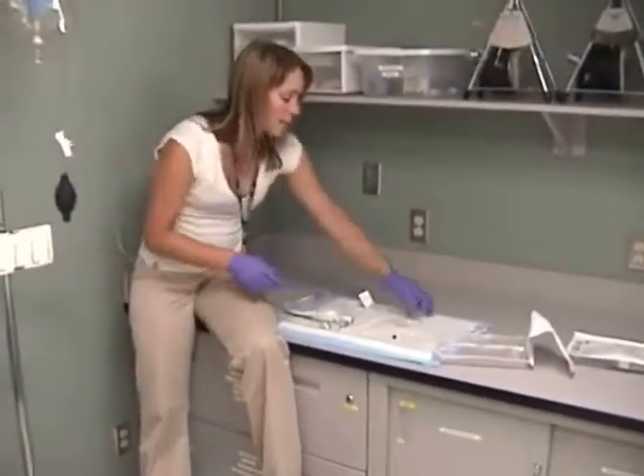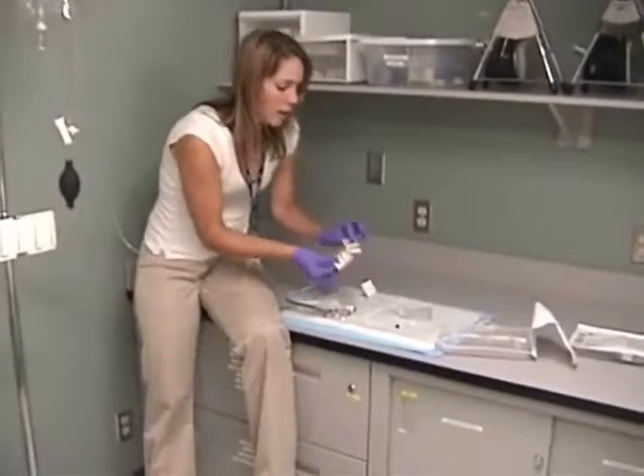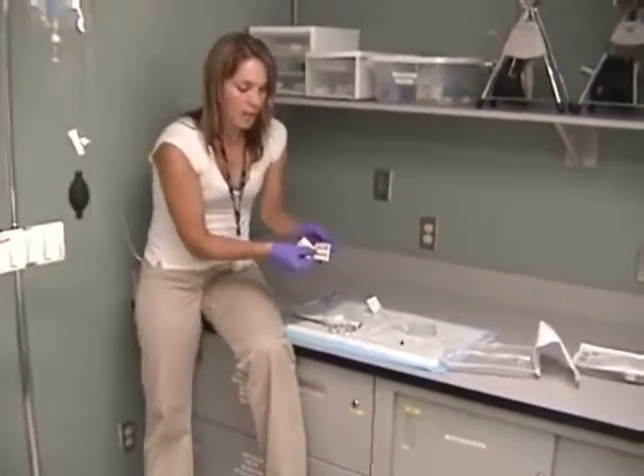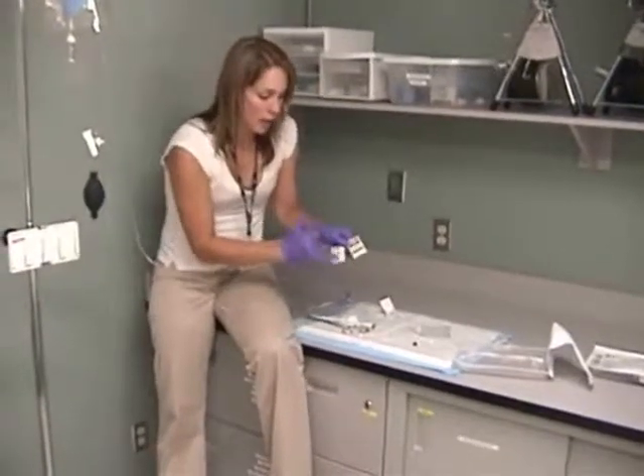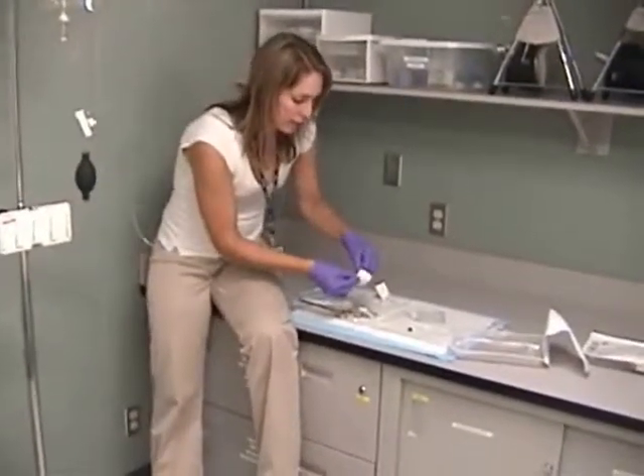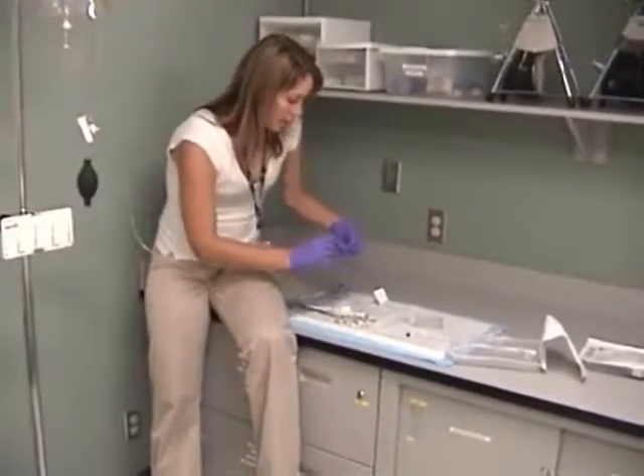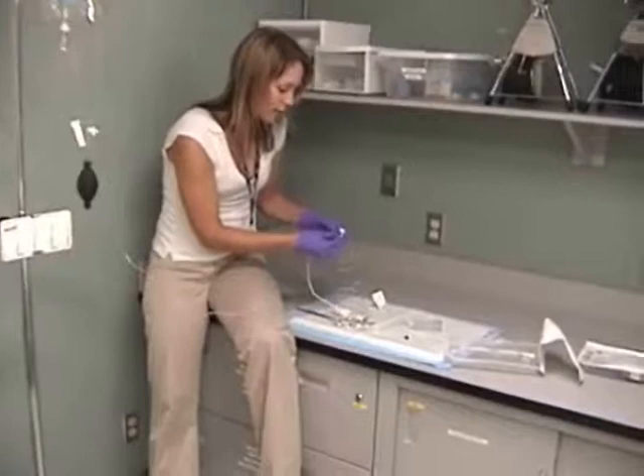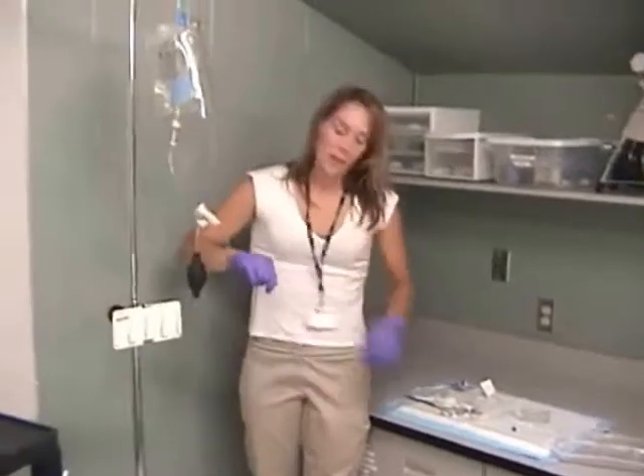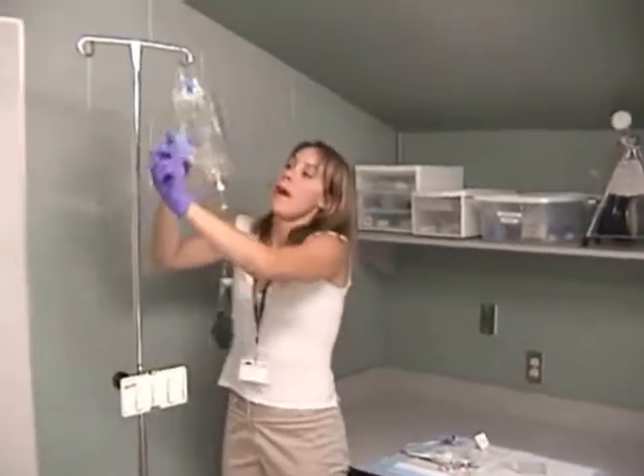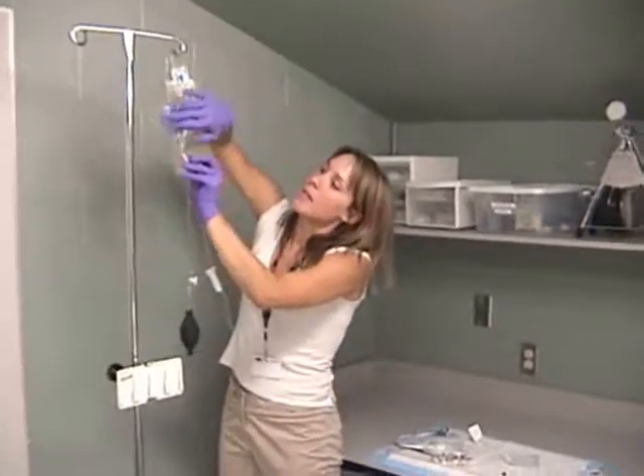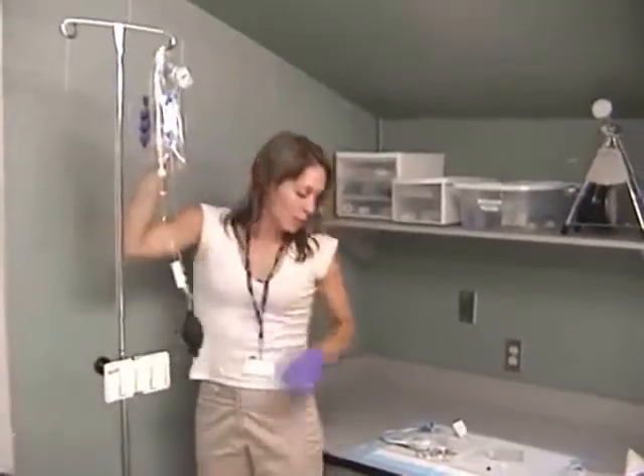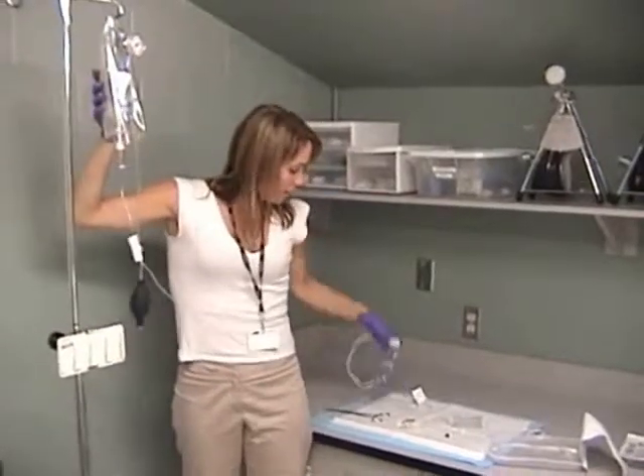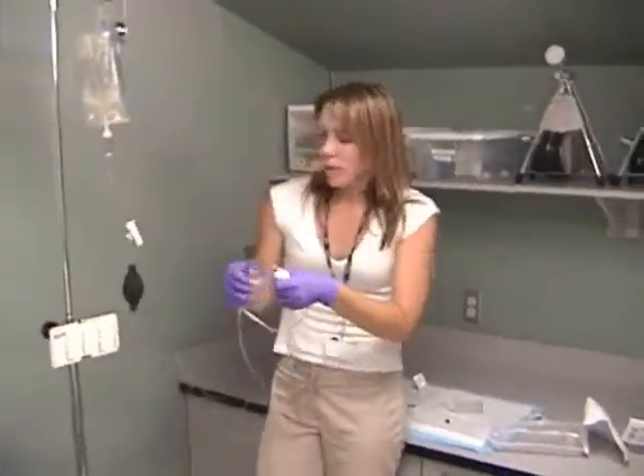Okay, the last thing you could do is the labels that come with this system are indicating arterial, CVP, or pulmonary artery pressures. Those are the most commonly monitored. So there are associated colors. Some people for the arterial line, for example, will take this little red dot and apply it on the stopcock so that the color system will match. Again, that is optional. When you're done with the pressure monitoring system here, you want to make sure you do up your pressure bag and pump it up to 300, because that's the pressure that we will use regardless of the site that we're monitoring. And again, the other thing you want to double check is your zeroing. So we will try to show you how to zero on the next video.